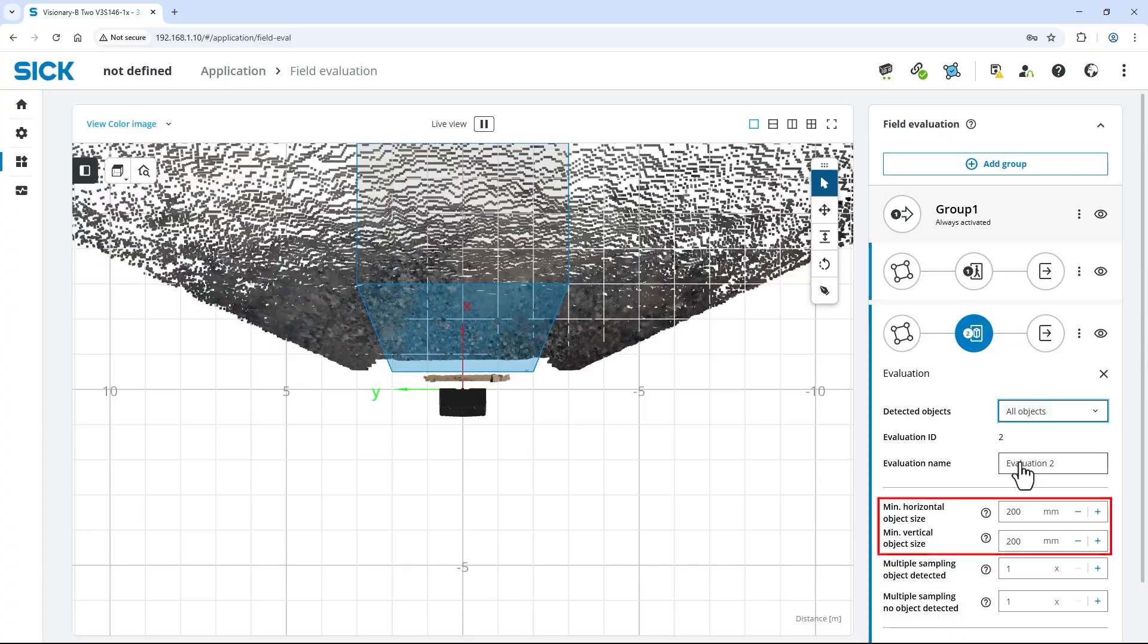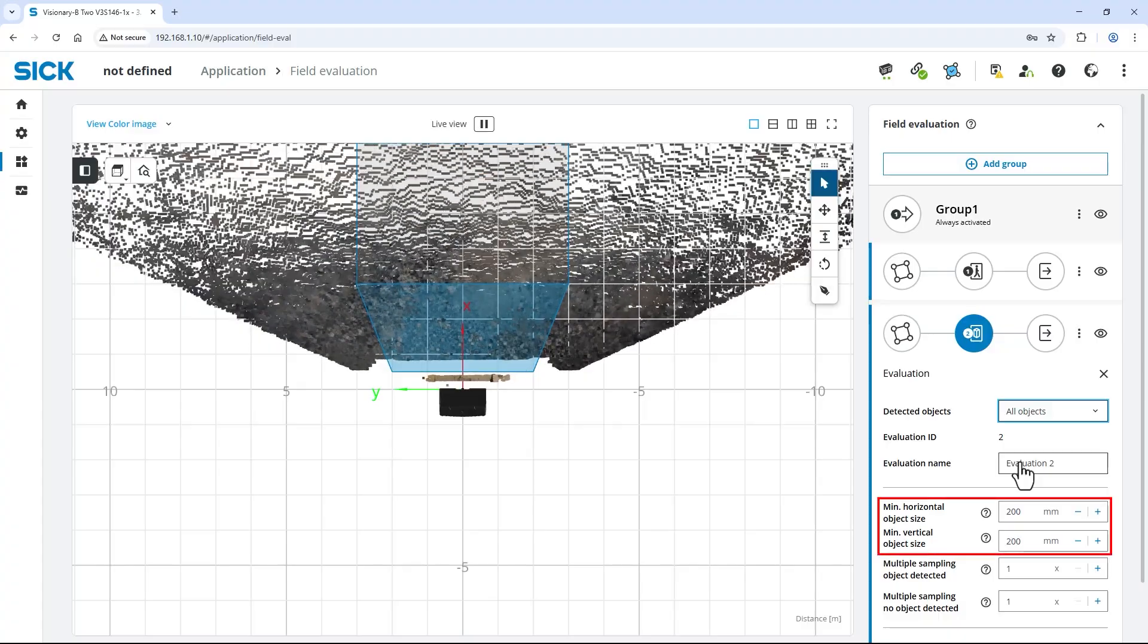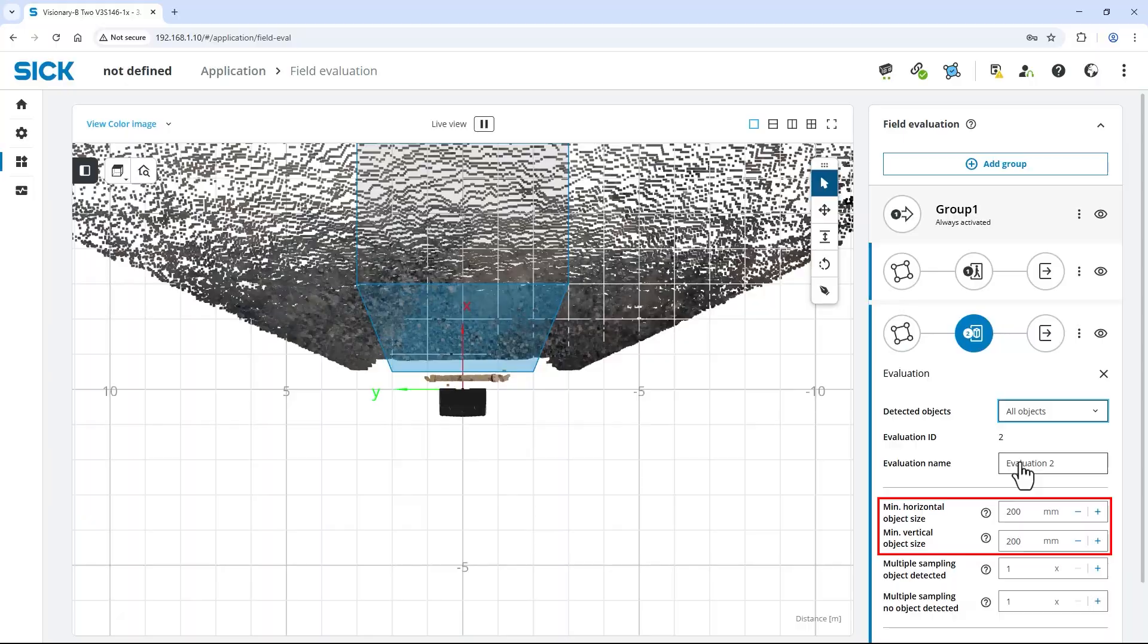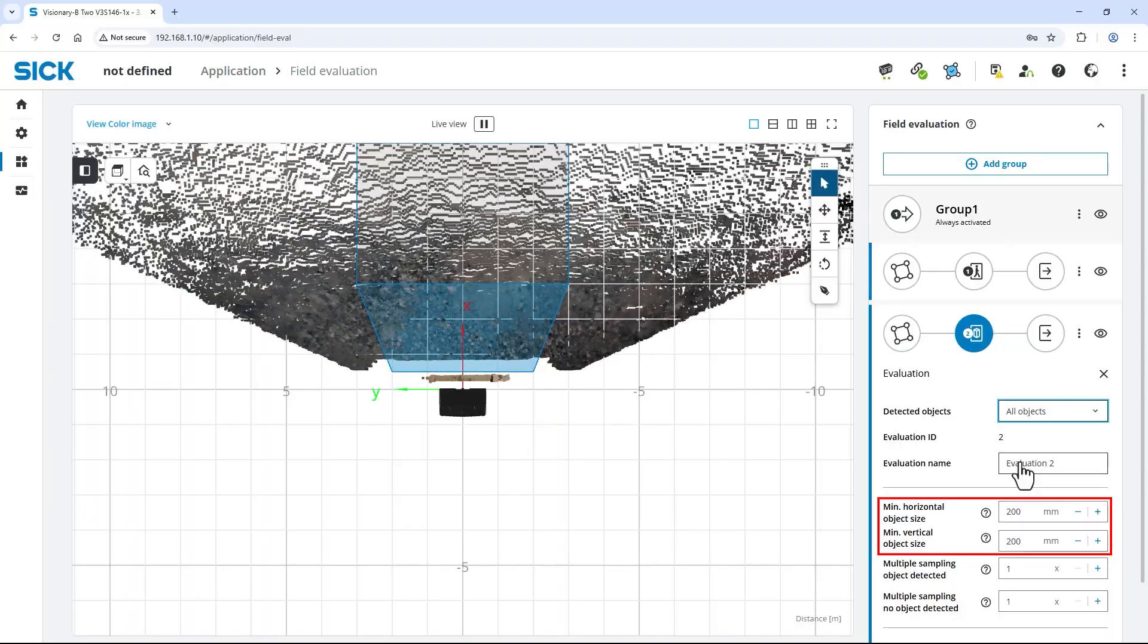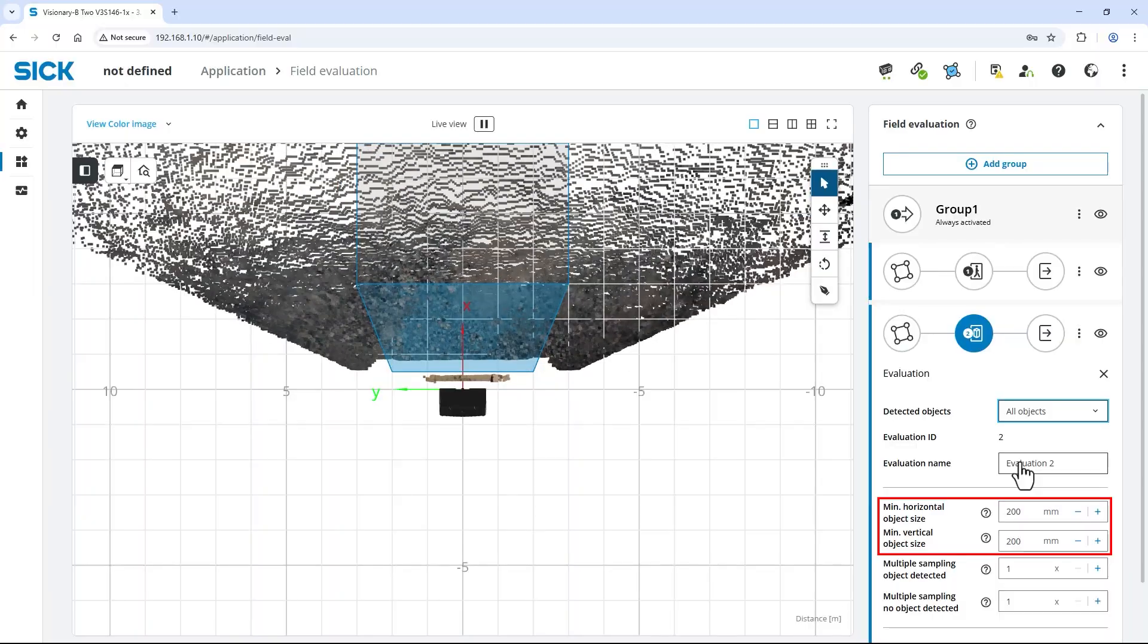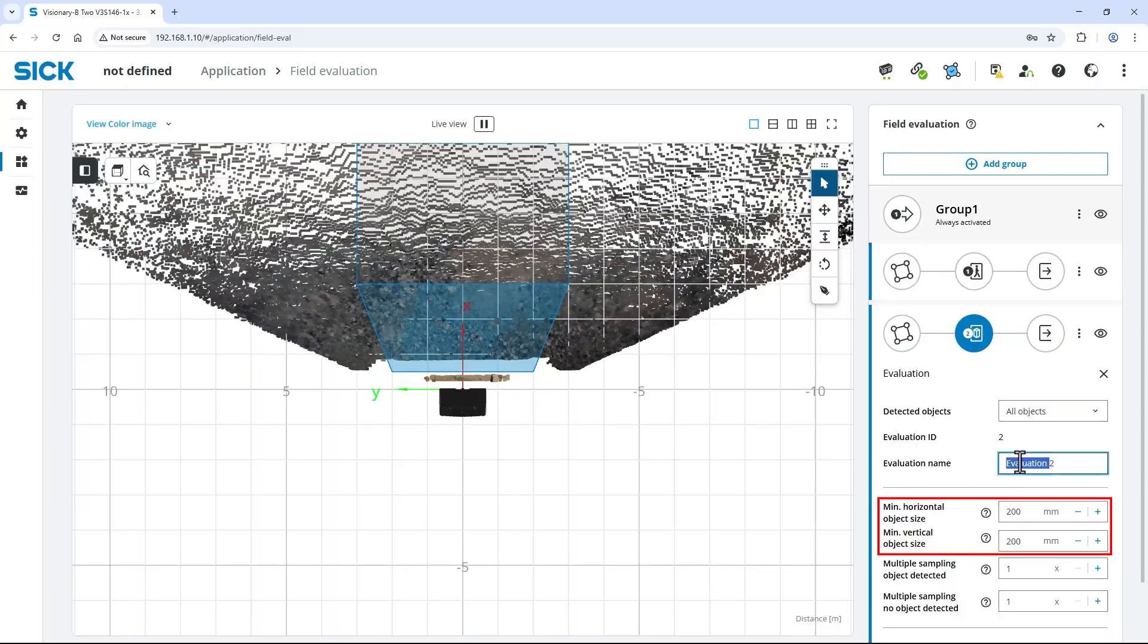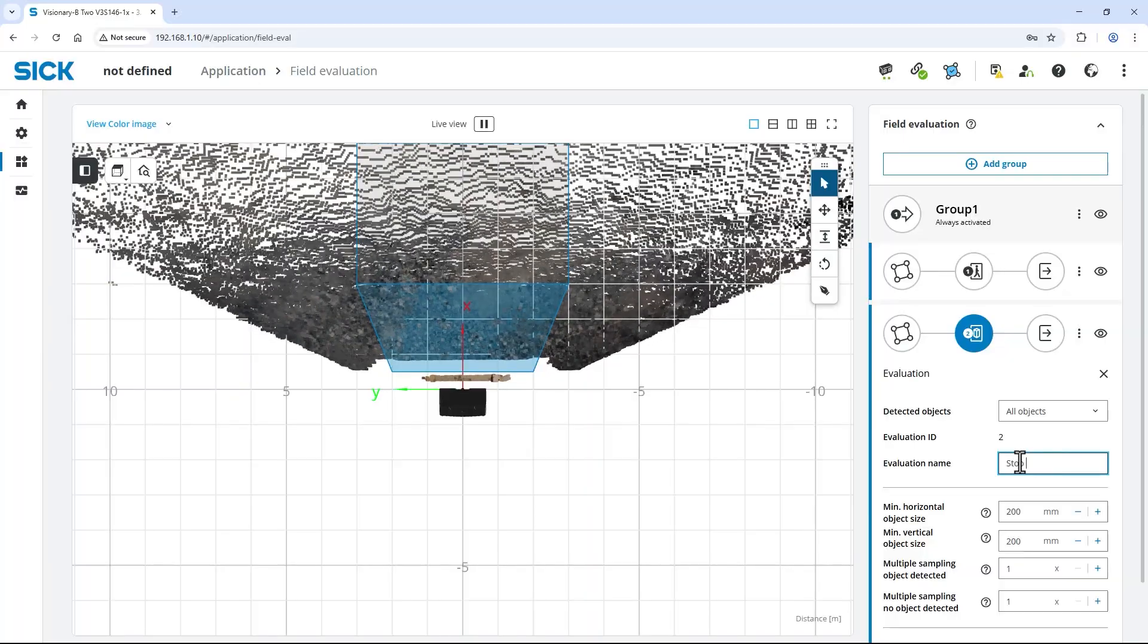By default, all objects larger than 200 by 200 millimeters are evaluated as a relevant obstruction. If needed, adapt the minimum horizontal and vertical object size to your needs. Last, change the evaluation name to stop field.